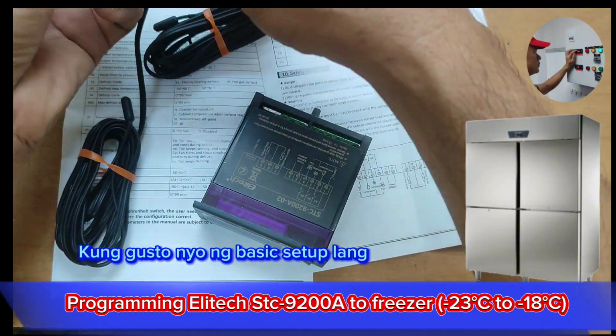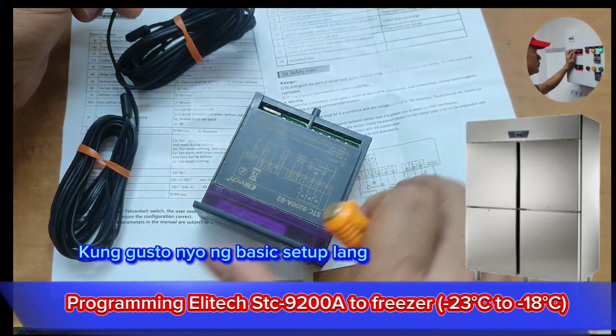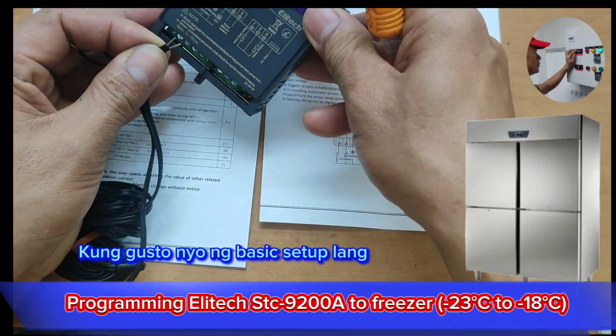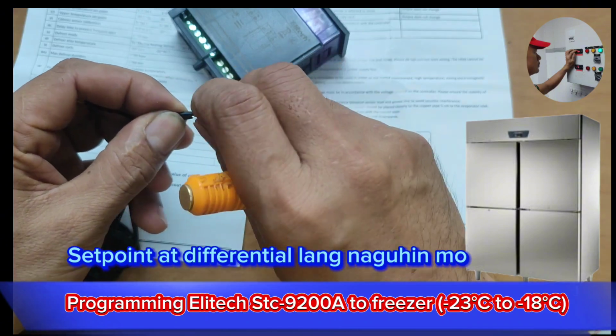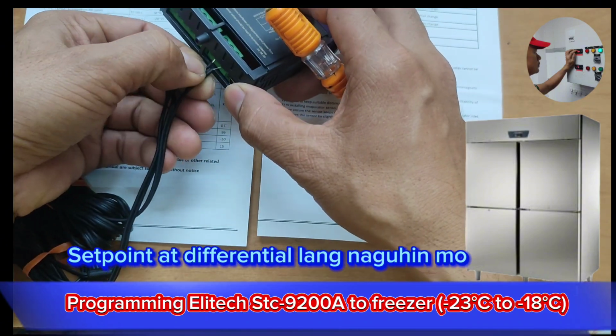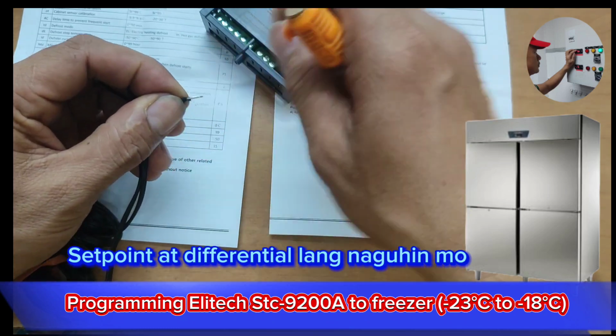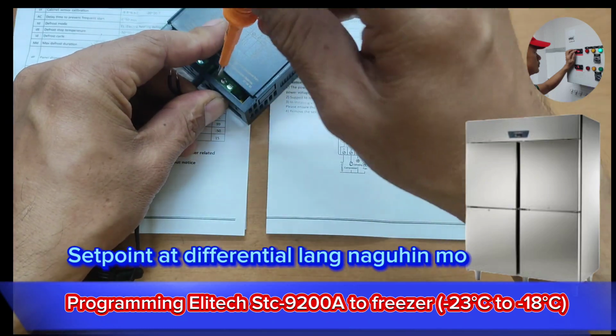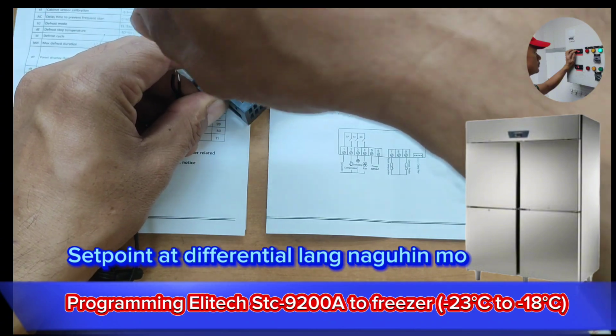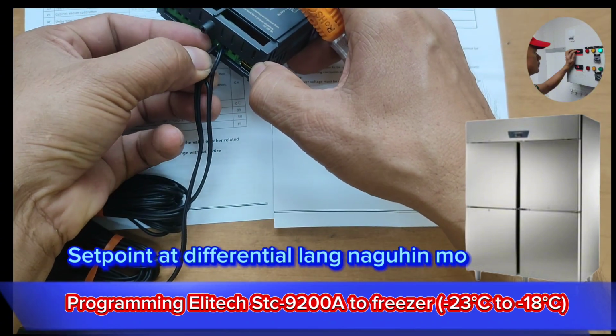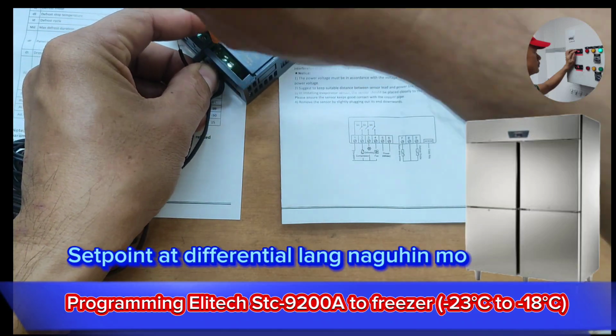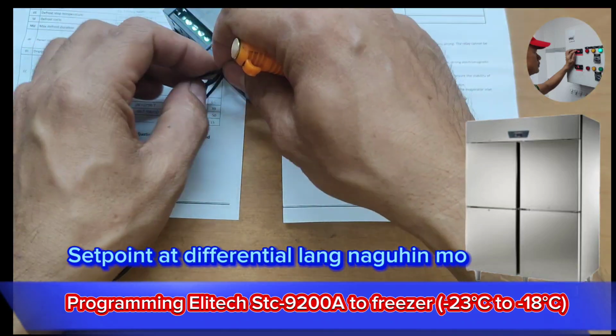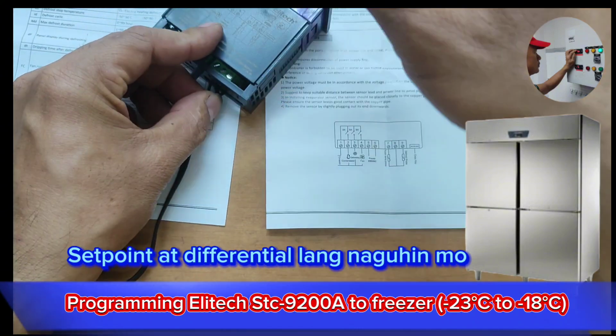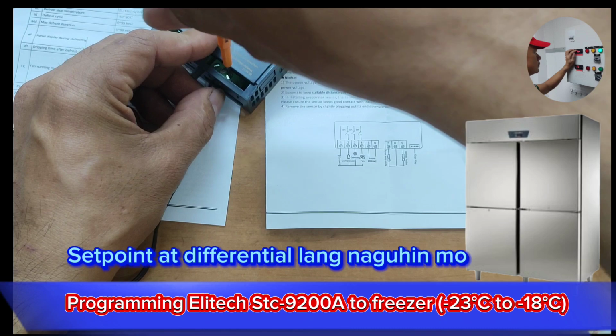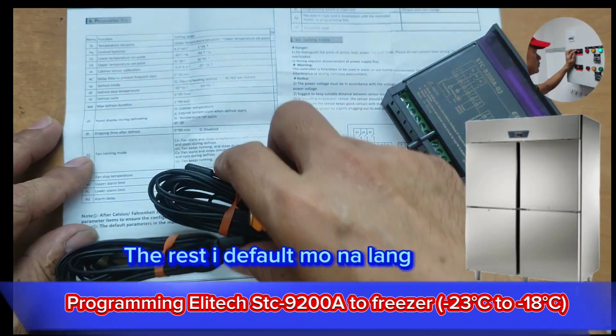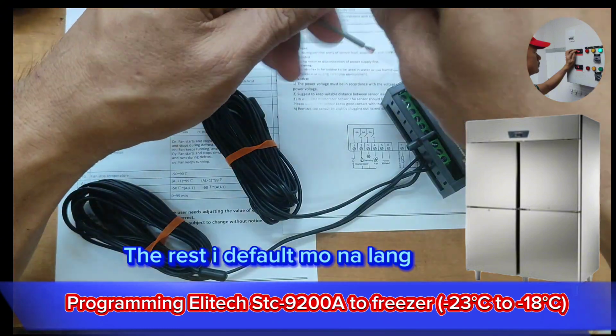I'm gonna show you how to wire it up. Just join the two here, and if you see terminal number 8, just plug these two into terminal number 8 there, and the other one to terminal number 7. Simple as that. By the way, this control is equipped for chiller and freezer. If you use it in freezer, make sure that you program all these parameters here, and that is what I want to teach you guys how to do.